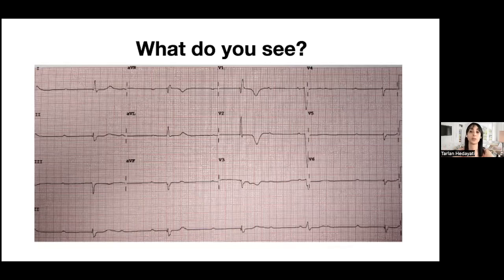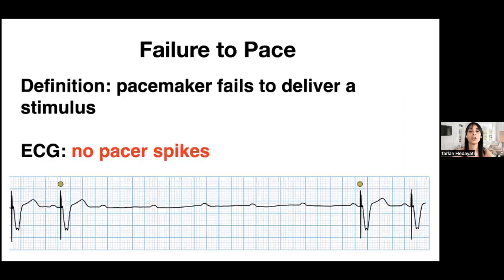So this patient's pacemaker is not working appropriately for whatever reason. This is failure to pace, and it's going to be the most common problem you'll run into with a pacemaker. This is where the pacemaker just is not delivering the stimulus, so you're basically not going to see pacer spikes.